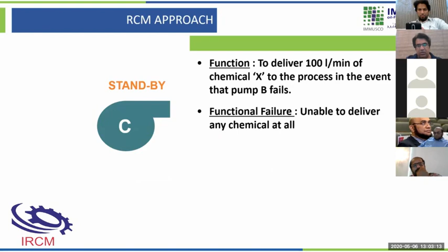Failure of pump C would not be evident to the operator under normal circumstances because until pump C comes into operation, you cannot assess whether it is working or not. So what will be the failure consequences? It will be hidden. So we have considered three different pumps, and for different operating contexts and functions they are actually meant for, we have defined different failure consequences.